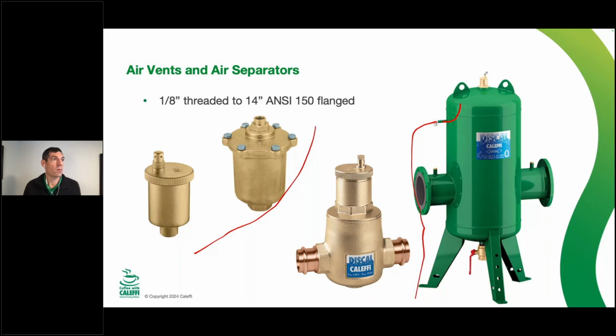Then you close that back up, and this isn't really needed anymore, and you put it back into automatic mode with the air vent at the top. That just speeds up the process a little bit, instead of getting an enormous air bubble to come out of that air vent. It might take all day if you were just going through here at the initial startup. So that's where you would use that gooseneck.